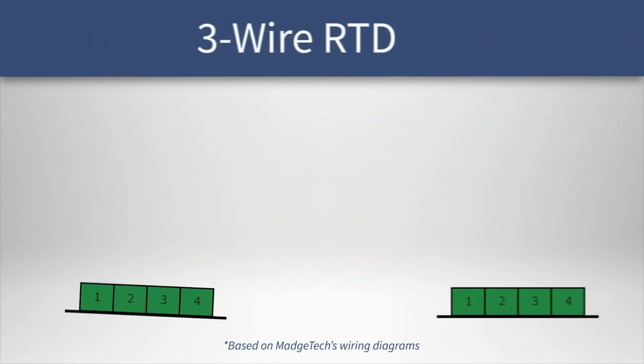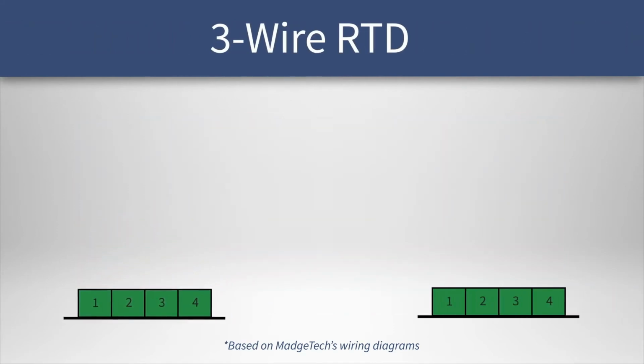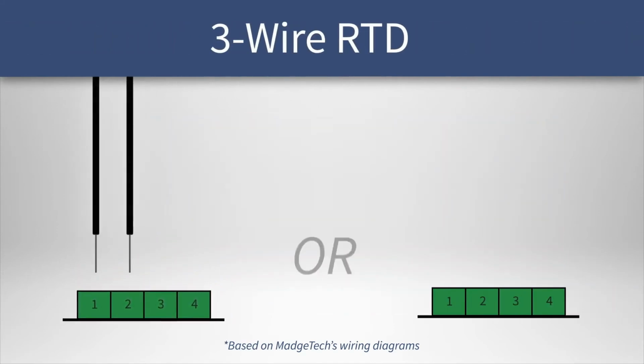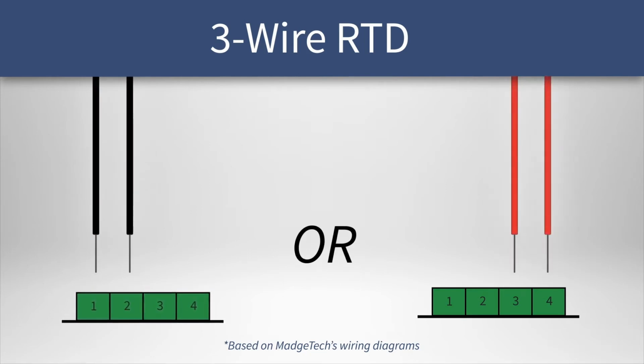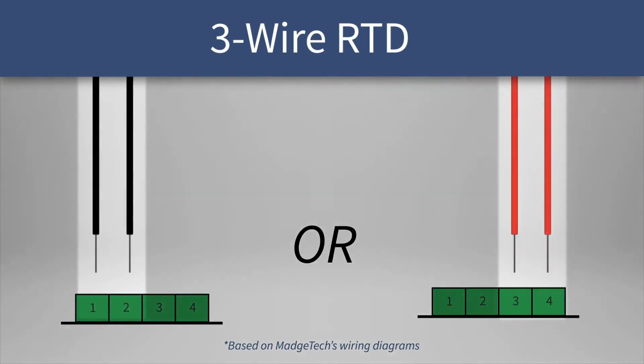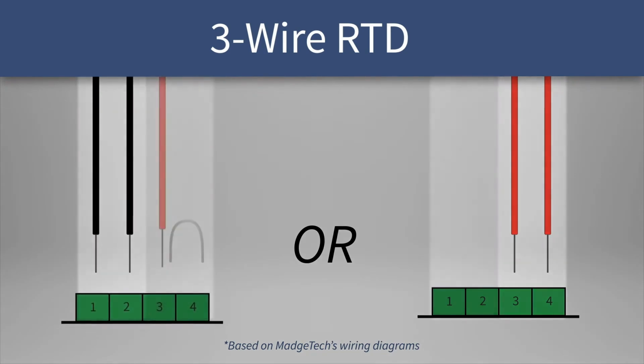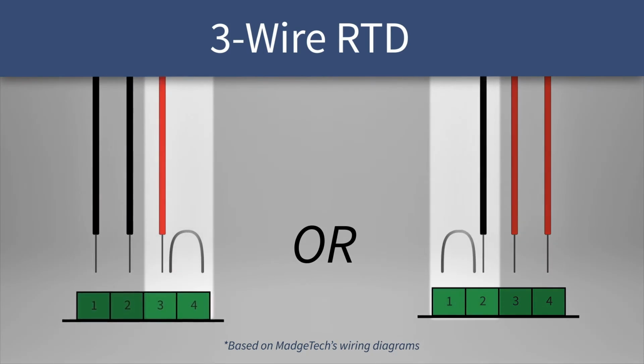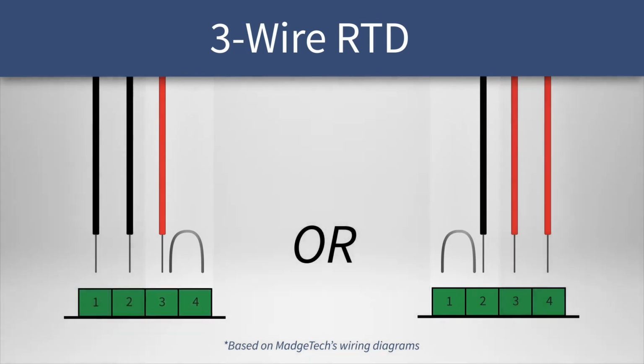With a 3-wire RTD, the color with 2 wires should be wired according to the 4-wire RTD instructions. For example, if we have 2 black cables, one black wire should be connected to terminal 1 and another to terminal 2. But the color with only a single wire should be wired and shorted according to the 2-wire RTD instructions. Mixing up the order of the wires will result in erroneous readings.